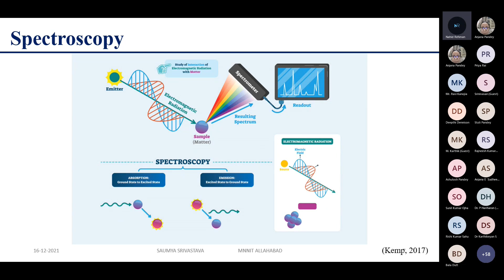In a spectroscopy instrument, different components are involved. First is the light source, by which the sample's compounds are excited by the electromagnetic radiation. The sample's molecules absorb the energy from the electromagnetic radiation, get excited, and jump from a lower energy ground state to a higher energy state of excitation. And a detector, which is usually a photodiode on the opposite side of the sample, records the sample's absorption of wavelengths and determines the extent of their absorption.